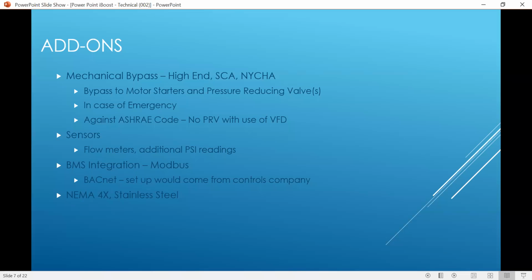If you wanted an upgraded panel with, let's just say, air conditioning, and it's an exterior location, we can do the 4X stainless steel with an air conditioner or a heater on there, and that keeps your panel at whatever temperature that you would like it at. But we try to recommend something around 100 degrees, no hotter than that. Although the new drives are all rated for much higher temperatures, that can actually go up to about 140 degrees and still maintain operation. So that's another reason we kind of use the ABB.